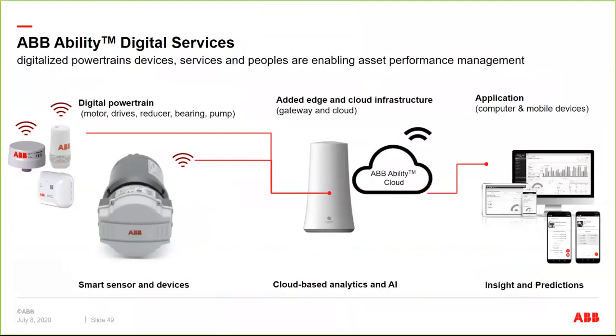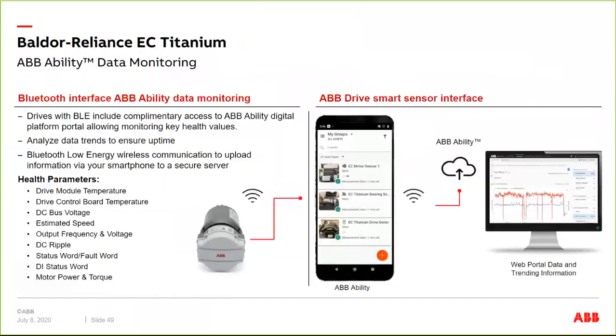All right. So here's what it looks like. It's basically a sensor that's embedded within the drive, and you can communicate to it. Either you can walk up with what's called the ABB Ability app on your mobile phone, and you basically look for the drive and connect to it, or we can do it with a hub here and pull the data out remotely. So here again is what it looks like. The parameters that we're monitoring in the drive are things like temperature, both the drive module and the control board, DC bus voltage. We're looking at speed, frequency, voltage, some status of some I/O, and then motor power and torque that could be used to do efficiency calculations for your actual energy use over time.